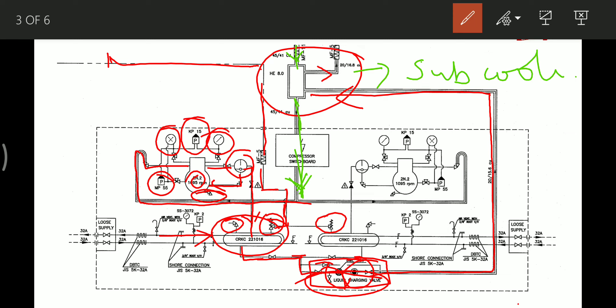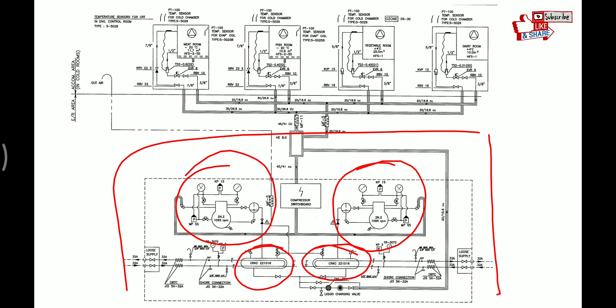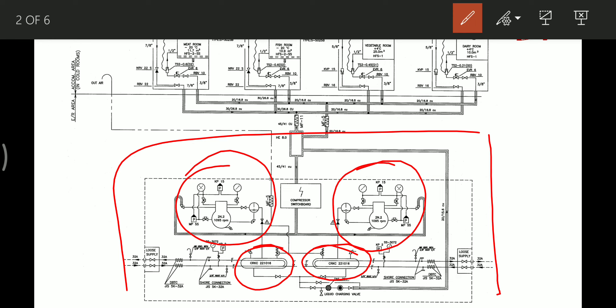This is all about the compressor and condenser unit in the engine room. Now going back to the full plant: from this point the refrigerant goes to four chambers. On board ship we typically have four chambers — the meat room and fish room, maintained at around minus 20 degrees Celsius, and the dairy room and the veg room, maintained at 4 to 5 degrees Celsius. From here the refrigerant goes to all four compartments.